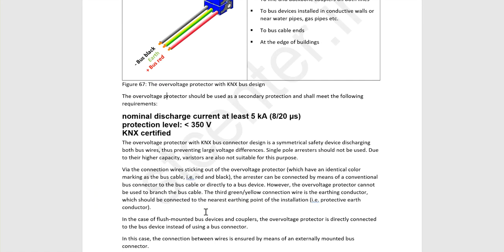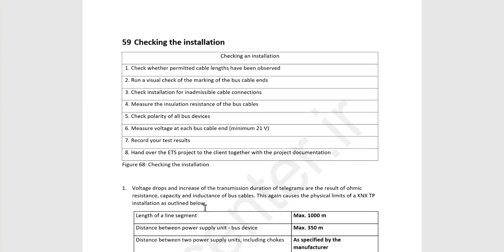Let's continue with that. So, after installation, what should we check? Check whether permitted cable lengths have been observed. Okay, we said 1000 meter maximum for one line segment. Run a visual check of the marking of the bus cable ends. Okay, we should know where the cable is coming from and mark it. Check installation for inadmissible cable connection. Make sure that the red and black are tight enough in connection with the KNX connector for all of the devices. Number 4, measure the insulation resistance of the bus cable.